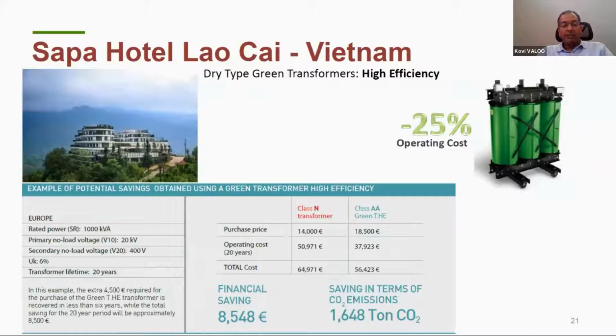Though the initial investment was a bit higher than a conventional transformer, the return on investment was achieved within 6 years. Knowing that the transformer's lifetime is 20 years, the customer benefits from savings for 14 years until the end of the transformer's life.